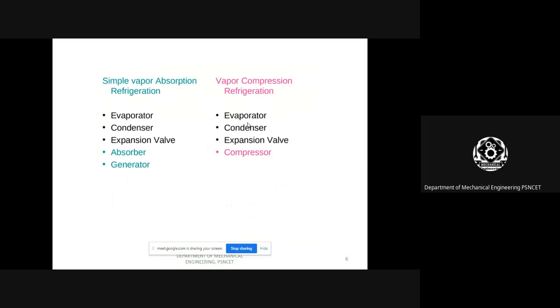Simply, refrigeration has two systems. One is the vapor compression refrigeration system, another one is the vapor absorption refrigeration system. The main difference between VCR and VAR is that the compressor is replaced by an absorber and a generator. So in this absorber, there is ammonia, lithium bromide, or water. Three liquids are used. Generator is mainly used for generating heat. So the vapor absorption system mainly works by means of a heat source.